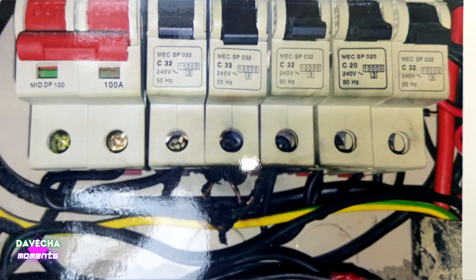If you don't replace this kind of wire, then this insulation will dry up and peel off, and this will pose more danger, caused by short circuiting by the earth or the neutral wire should they come in contact with this live conducting wire. So be well informed about these loose connections for you to be safe when you use your electricity.